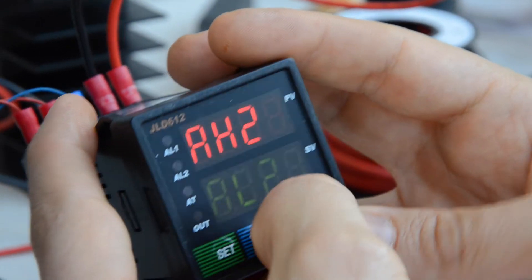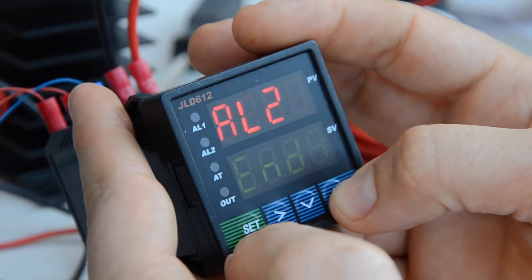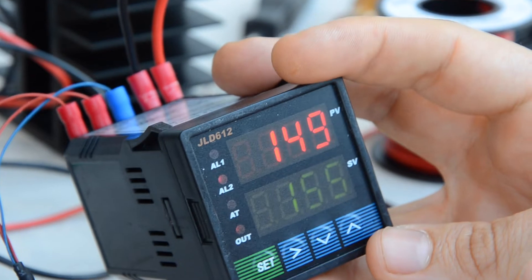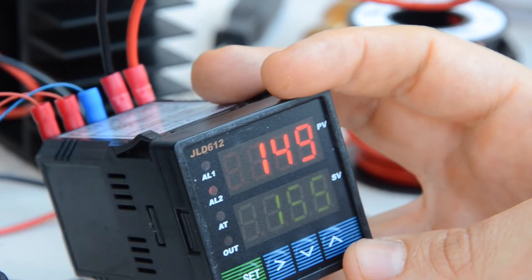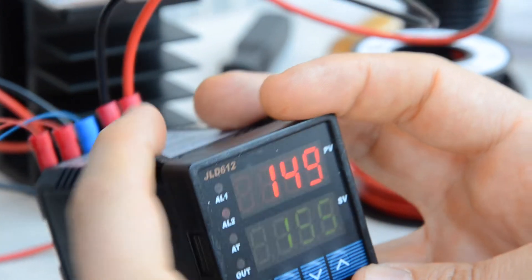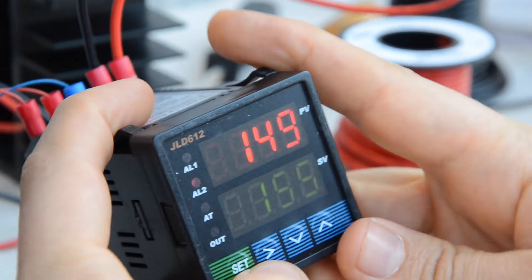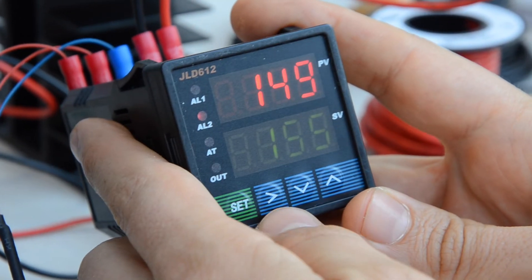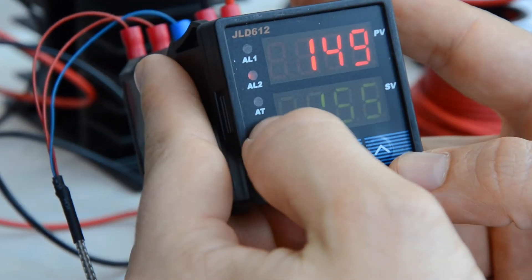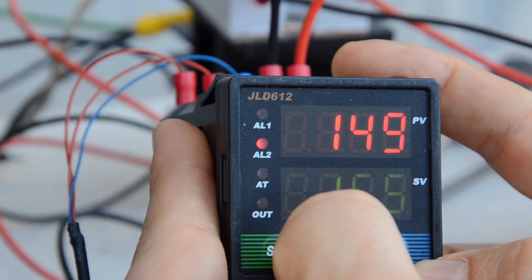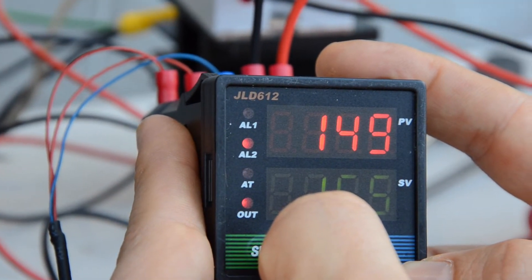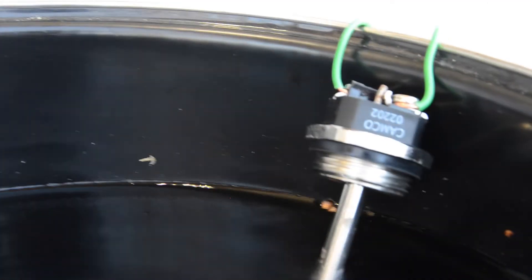And that's the entire setting on that one. So now, to get it to tune itself, because it is auto-tuning, those are the easy parameters you can set. The other ones involve crazy integrals and derivatives and very ugly equations. So you hold down this right arrow until the AT, which stands for auto-tuning, starts flashing. So I'm holding it down now. Okay, it's flashing now.